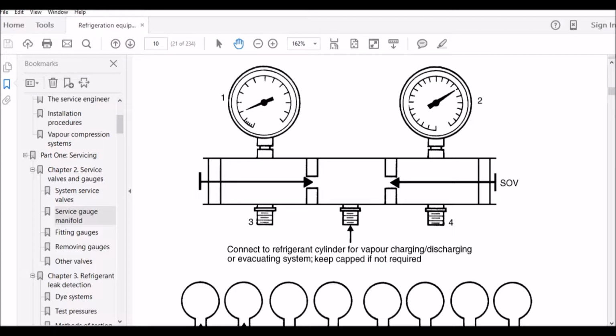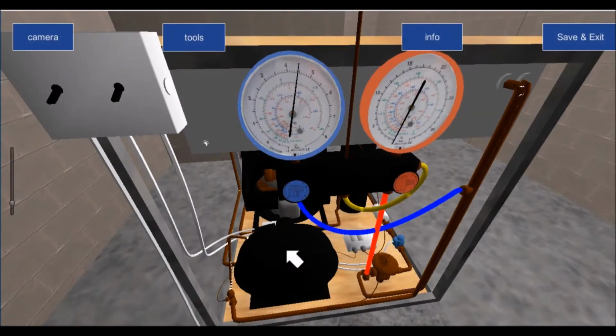The analog gauges that we're looking at here, which are the mechanical gauges, are basically bulletproof to a certain extent, and the digital gauges are more expensive, and you have to mind them, and you have to make sure that they're calibrated as well. So you'd have to get a calibration cert to make sure that the digital reading is correct, whereas the mechanical, we can actually calibrate ourselves. Basically there is our calibration nut here. So there's a little plastic covering.